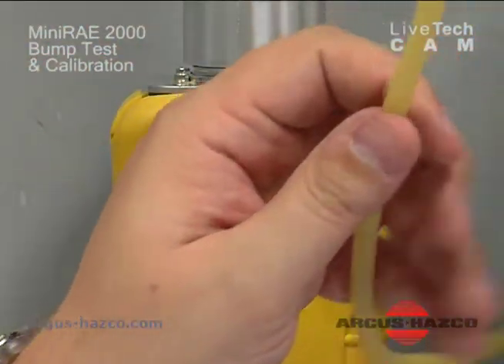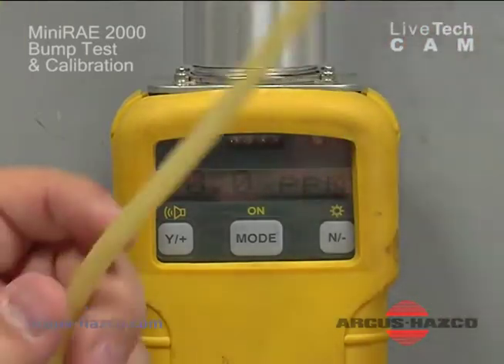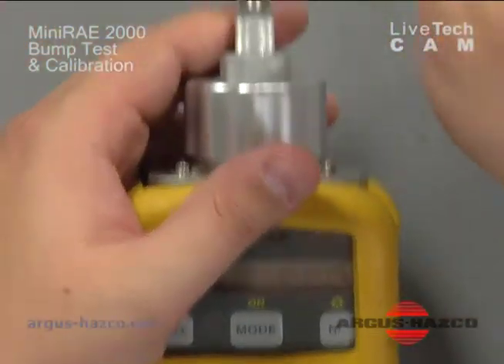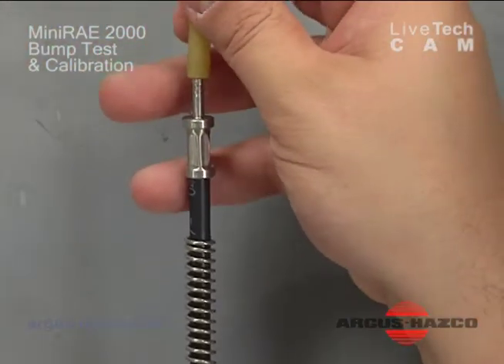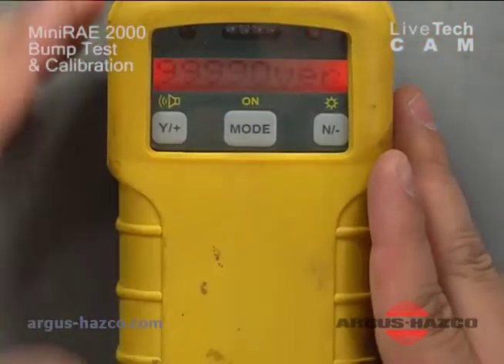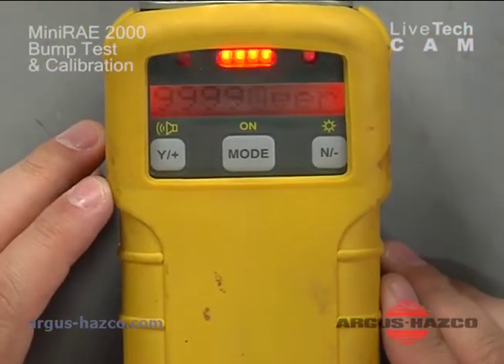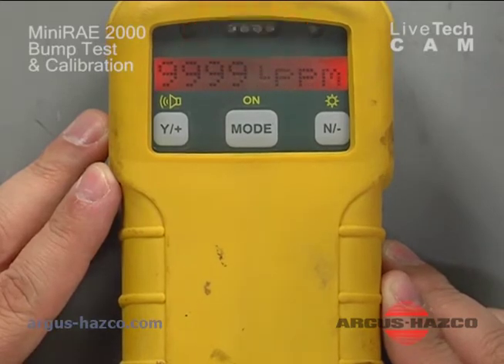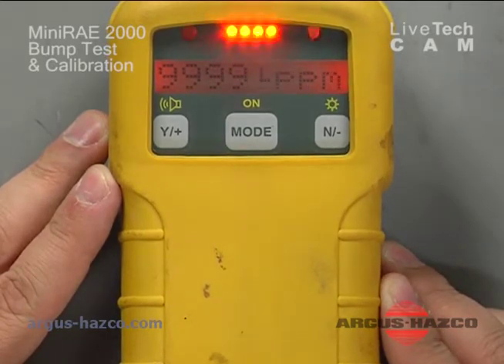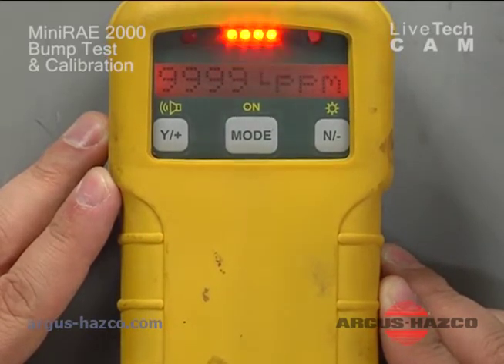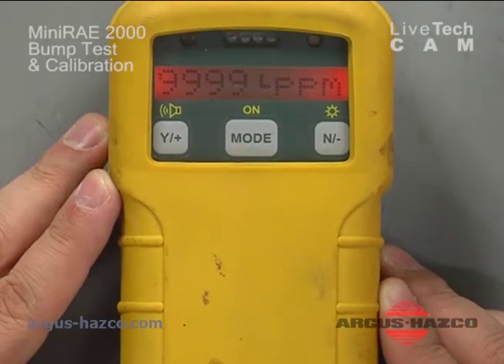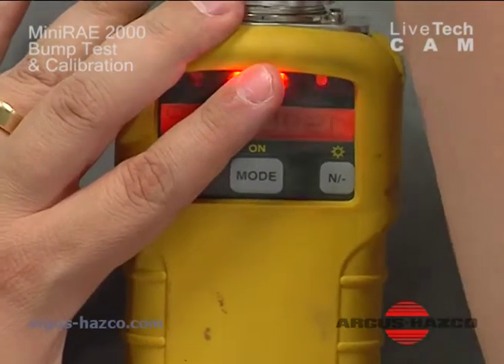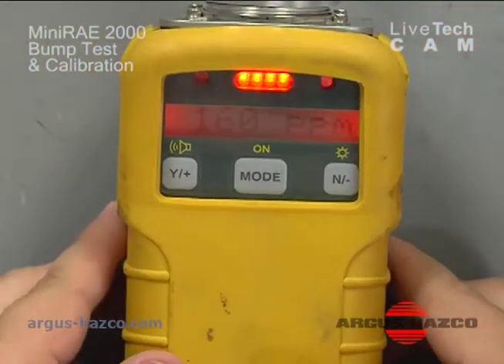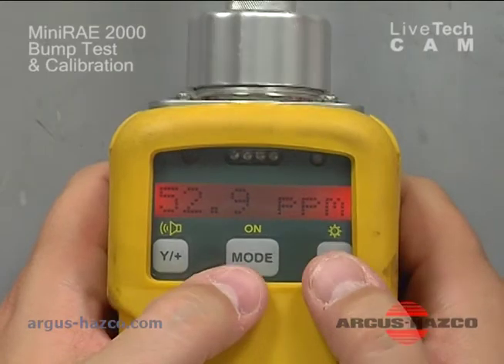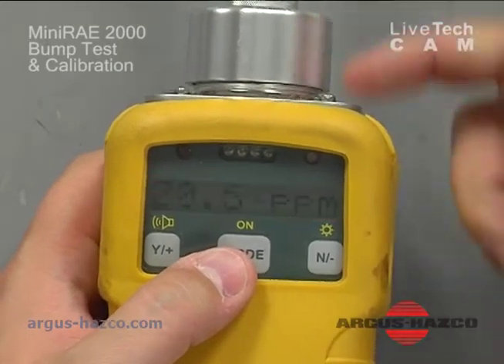We're going to turn the valve on the cylinder to dispense the gas and connect that to the inlet. At this point, it's giving you an over indication, which is telling me there's more of a problem than just a bump test. So at this point, we may need to calibrate. We will need to calibrate this instrument. So we're going to disconnect the gas. Let that reading come back down. Give it a few seconds to purge the fresh air through the system.